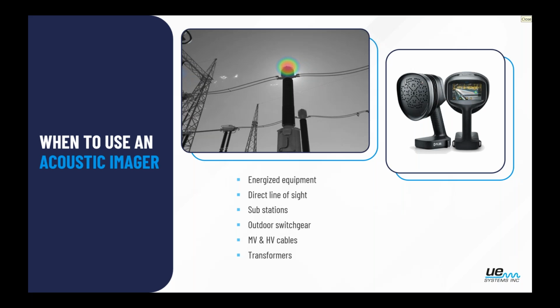Just like with an ultra probe, we're really not trying to inspect the winding inside it, because that would be a contact method. We're not looking to inspect gas insulated equipment. This is things that you could have direct line of sight on. Once again, very similar to an infrared camera. We want to be able to see what we're inspecting with an acoustic camera.